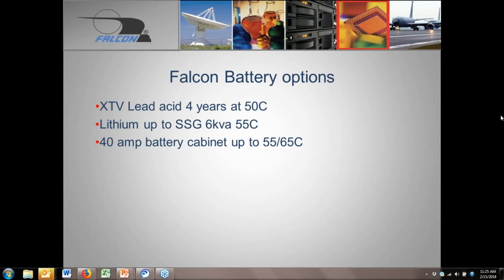So you actually don't recommend doing it, do you? No, it's not necessarily required. Like I said, 6 months to a year, if that's a normal PM schedule for any equipment. But if there's anything that would be done every few years, then yeah, that would be the most we recommend. For the most part, the scheme of the charger, the way it floats, and the voltage level we're at for the battery is well under the maximum rating, and that prolongs the life of these batteries overall. So the maintenance is kept very low because of that.